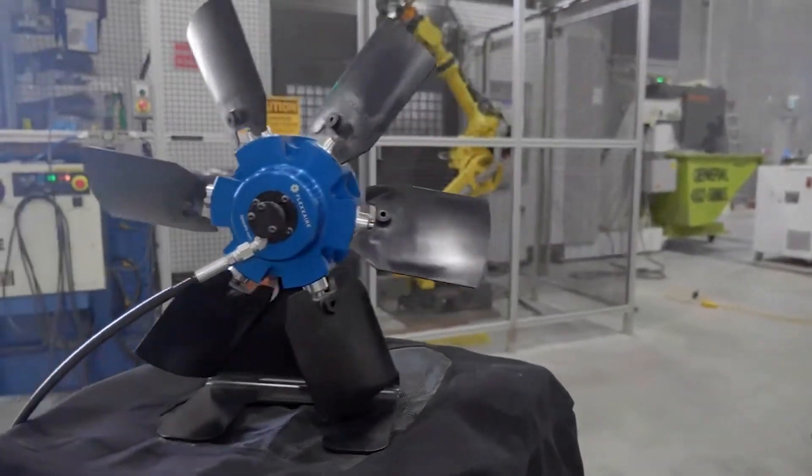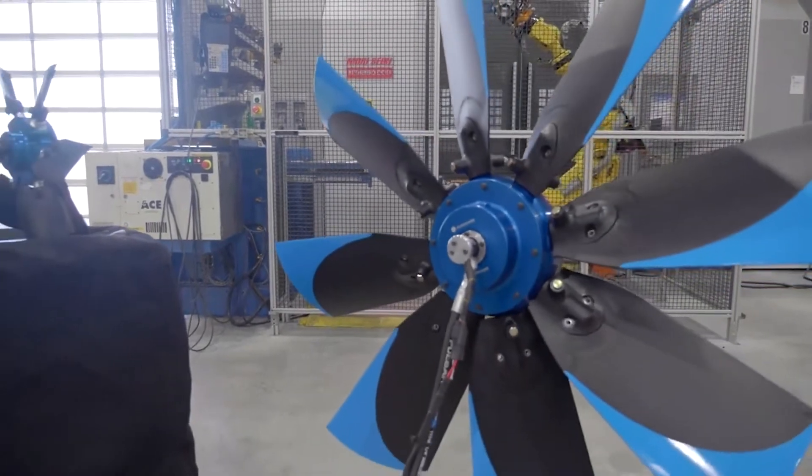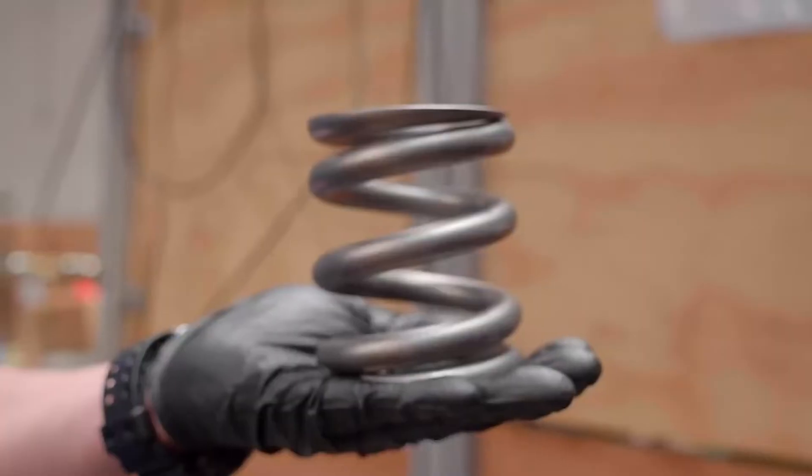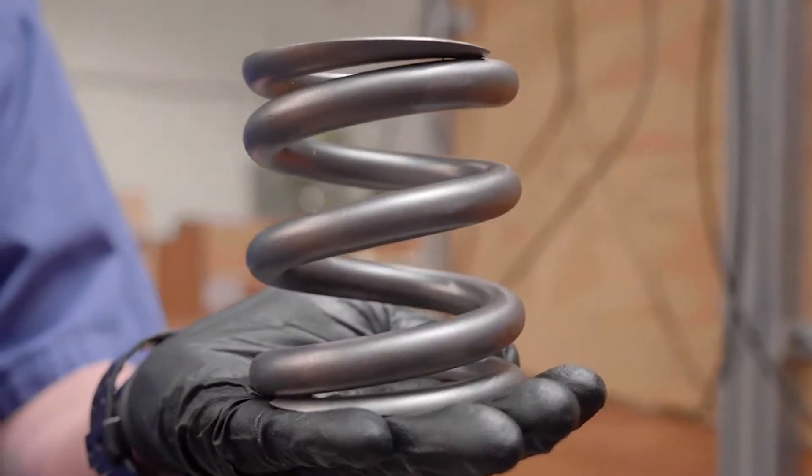The Flexair fan was engineered and designed to be intrinsically safe. If there is a loss of pressure to the fan, the spring return piston will automatically set the blades to maximum cooling pitch, allowing the engine to continue operating without overheating.